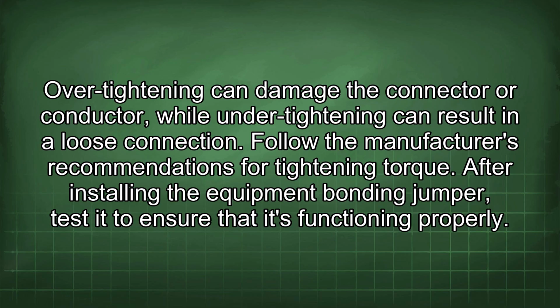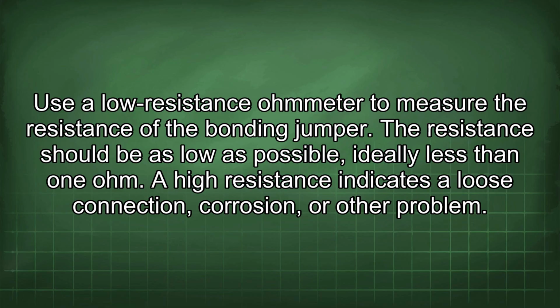Over-tightening can damage the connector or conductor, while under-tightening can result in a loose connection. Follow the manufacturer's recommendations for tightening torque. After installing the equipment bonding jumper, test it to ensure that it's functioning properly. Use a low resistance ohmmeter to measure the resistance of the bonding jumper.